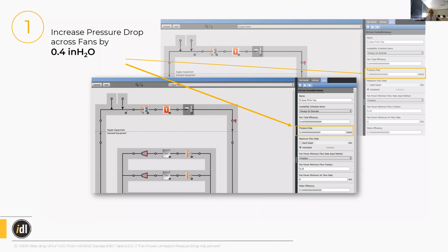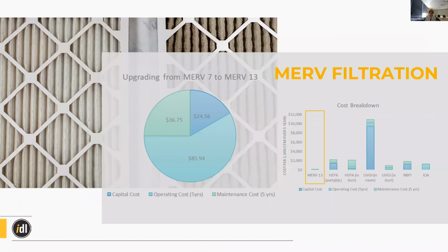So going into the modeling a bit, this is just a couple of screen grabs of the energy model that we did for MERV filters, for upgrading from a MERV 6 filter to a MERV 13, which ASHRAE recommends. And really the only thing that we needed to model for this one was the increase in pressure rise across that filter. So your fans have to work harder to push the air through the finer mesh of the MERV 13 filter. And so from our research, pulled from a lot of different sources, basically we calculated that out to a 0.4 inches water gauge pressure rise. So this was a pretty straightforward model. Plug that in, and then here is the breakdown of what that model came out to.